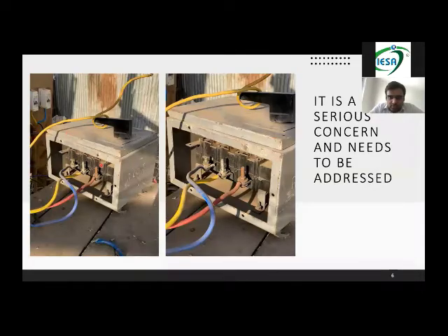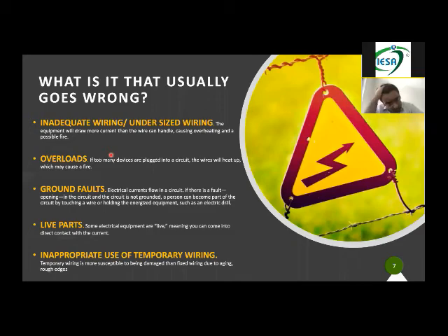Loose cables, no lugs, open ends of the cables, aluminum cables are being used. This is a changeover. If you have any technicals on site, sound, light, LEDs, or you are creating a backup, so a manual changeover. All those things need to be addressed. Otherwise, one day there is going to be a problem on site. So again, what is it that usually goes wrong when something goes wrong in an event?